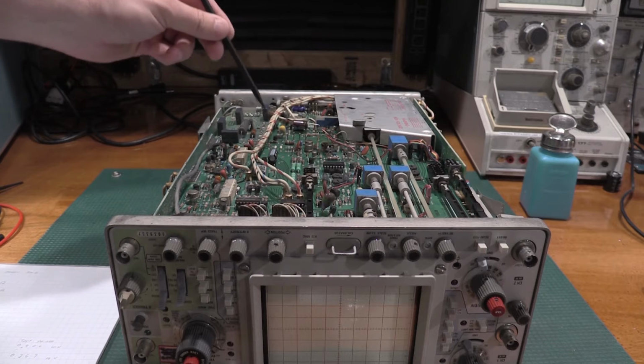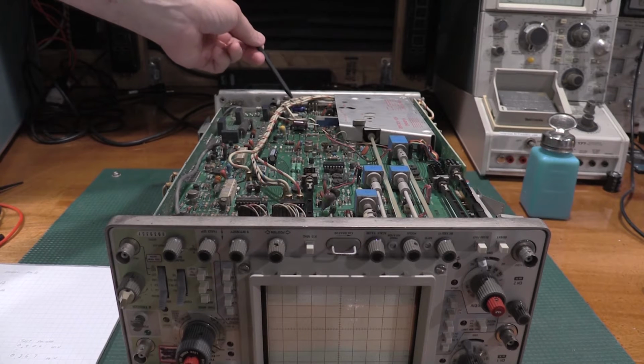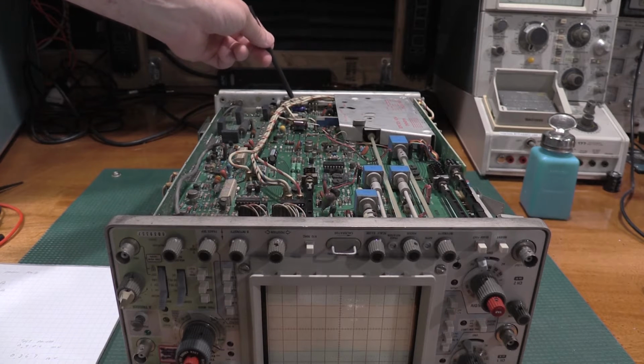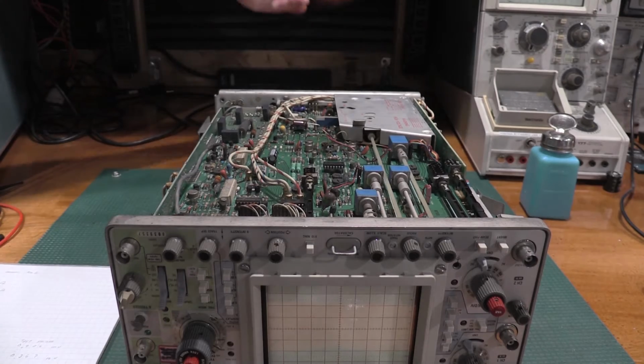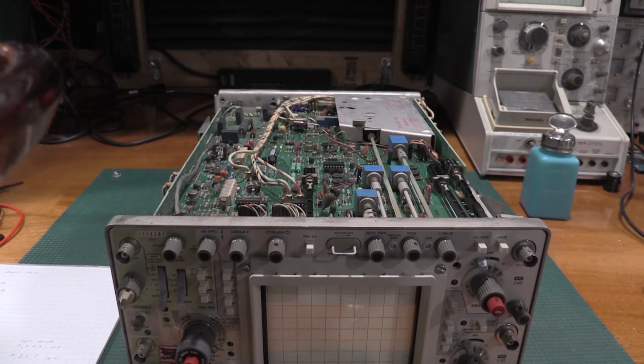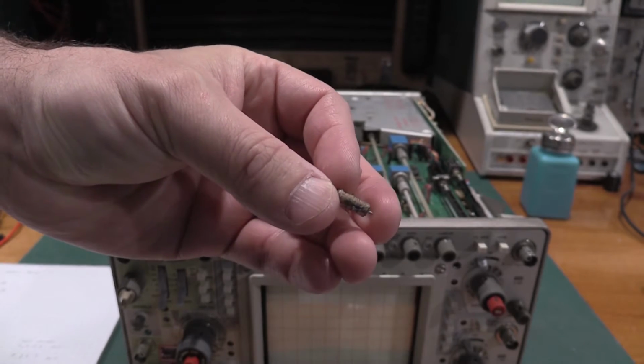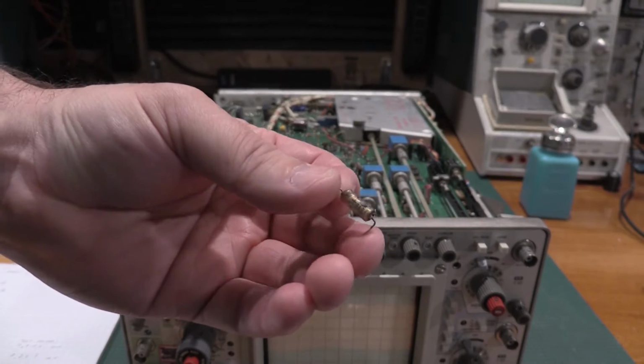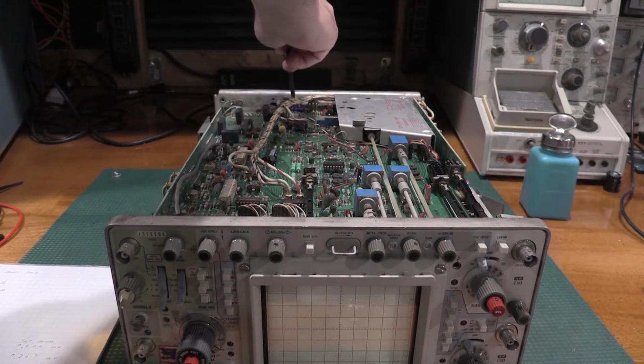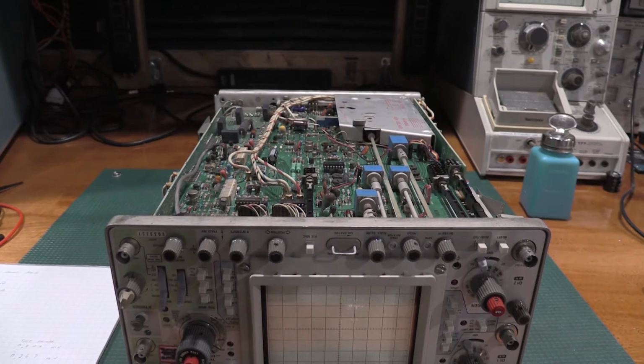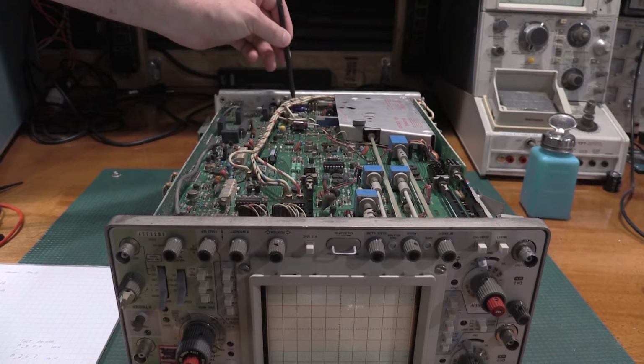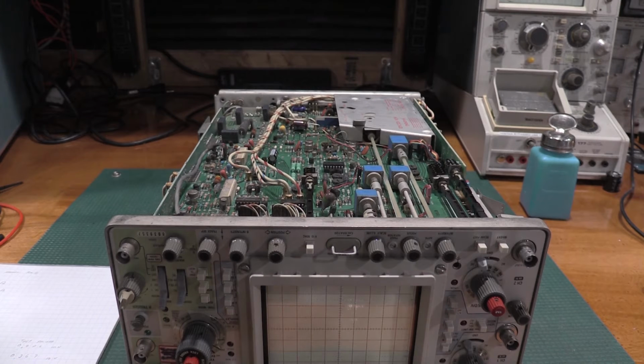This cap has been replaced, this cap has been replaced, and underneath this bundle of cable, if you're ever working on a 465, make sure you check this cap right here. That is a tantalum capacitor, and I don't know if you guys can see that, but that cap is corroded, cracked open, and is not healthy. That's the cap that was right back in here. So anytime you open up a 465, make sure you look at this one for sure. Make sure it's not blown open. These two just had a little bit of high ESR, so no big deal.